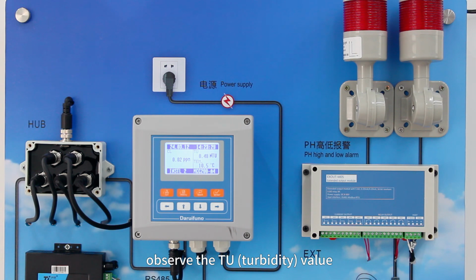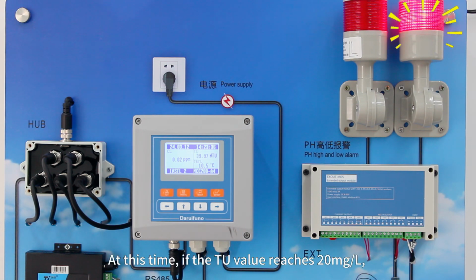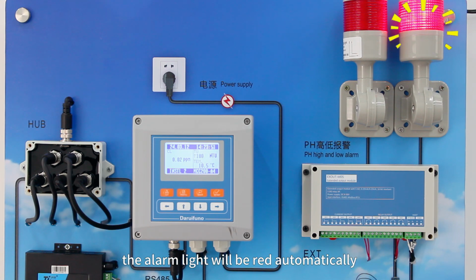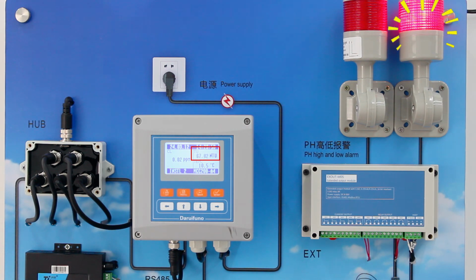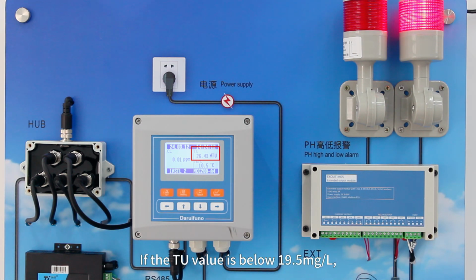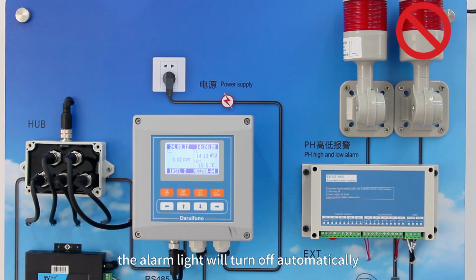Observe the TU turbidity value. At this time, if the TU value reaches 20 mg per liter, the alarm light will turn red automatically. If the TU value is below 19.5 mg per liter, the alarm light will turn off automatically.